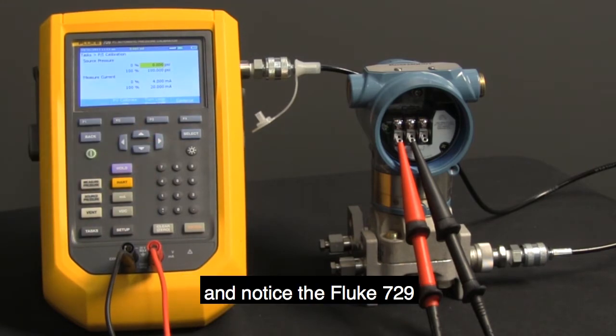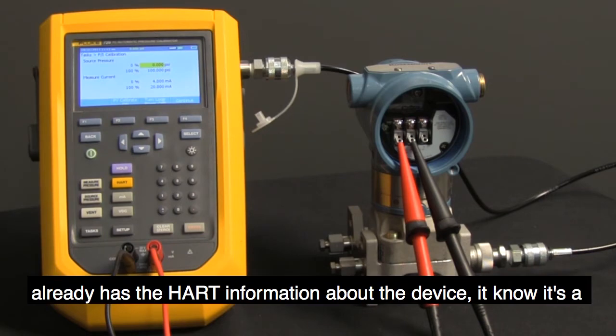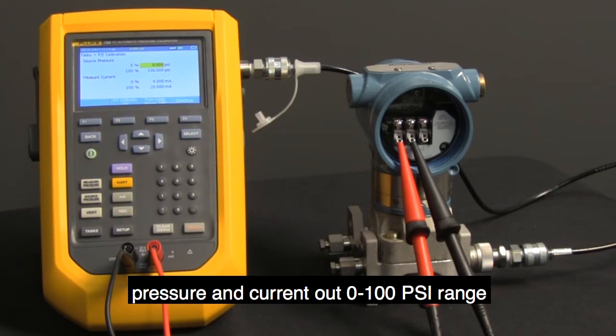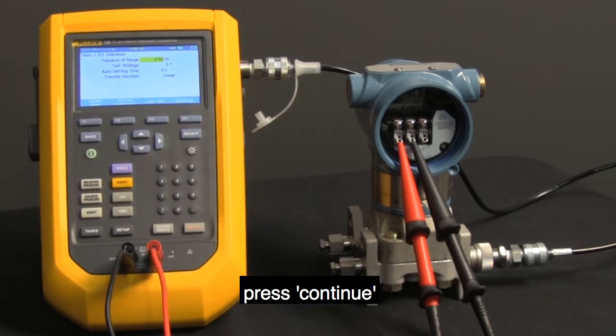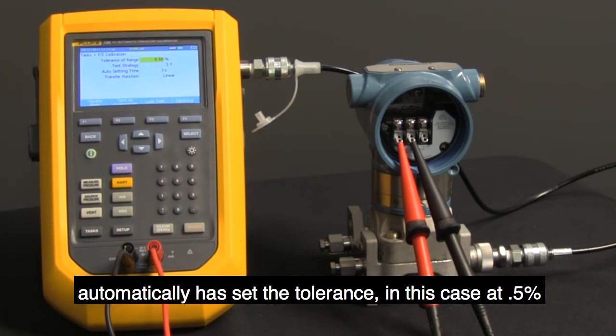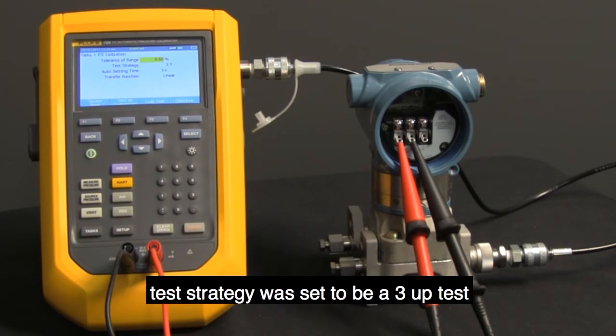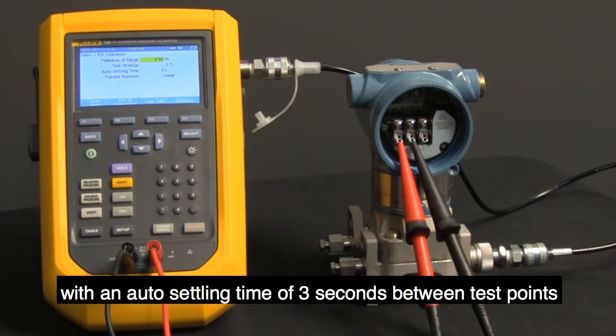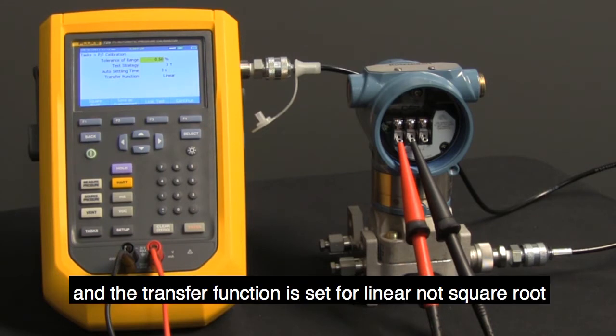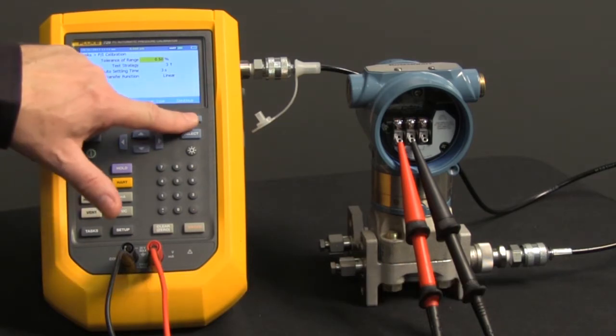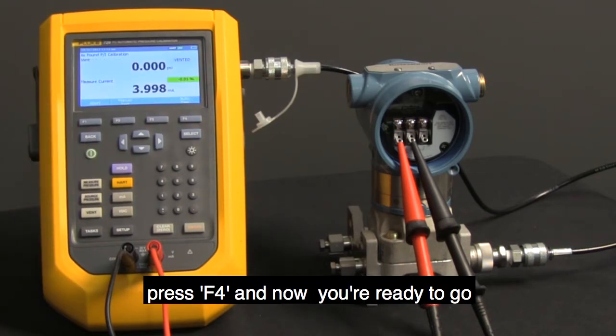And notice the Fluke 729 already has the HART information about the device. It knows it's a pressure in, current out, 0 to 100 PSI range. Press continue. Automatically has set the tolerance, in this case at 0.5%. The test strategy was set to be a 3-up test with an auto settling time of 3 seconds between test points, and the transfer function is set for linear, not square root. Press F4 and now you're ready to go.